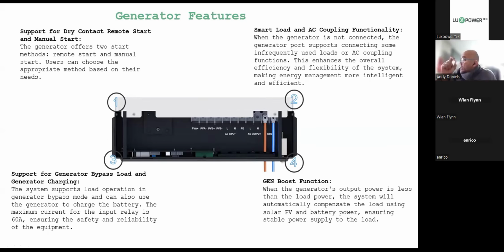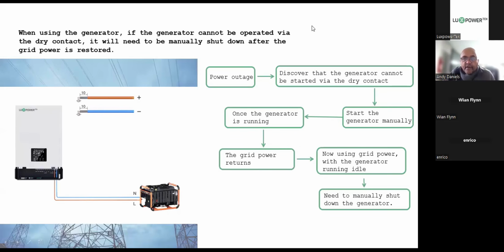What does it do? If you are running a generator and there is PV available and the generator is underpowered, for instance, you might have a 2 kilowatt or 3 kilowatt generator and you've got PV available, you can enable the boost function. What this inverter will do is use PV to assist charging the battery and take load. Very cool feature. I highly recommend you try it if you have that requirement. Okay, so remember that when you're using a generator, if the generator cannot be operated by the dry contact, then you'll need to manually shut it down after the grid power is restored.